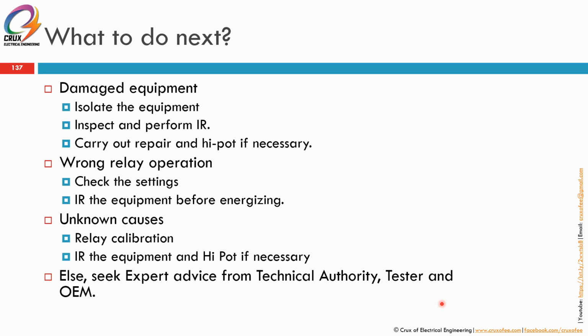So when you have found and collected all the information, what do you do? Number 1, make it safe first. Don't reset the relay yet. Number 1, the damaged equipment we have to isolate first. Isolate the equipment, rack out, prove the circuit dead, discharge and earth the equipment. Then you go to the equipment, remove the earthing, then inspect and perform the insulation resistance test and everything. If the damage is very bad, carry out the repair and hi-pot if necessary.